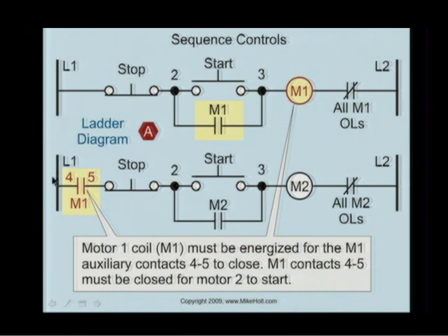I think this is another stop-start circuit for motor two, a separate one. Okay, so now this contact closed, but that motor hasn't started. Correct, because this coil had to be energized to close the contact in a separate circuit for a separate coil. Now that this is closed, I press the start button. Now I can start the next piece of equipment or energize the next M2 coil, which closes the M2 contact, which now interlocks the M2 coil. Now the second stage can continue to operate.